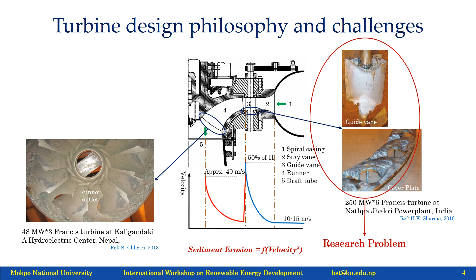So there have been some measurements in the power plants. In the same power plant, the biggest power plant in Nepal, the gap between the guide vane and the cover plate has been measured. So this is the reference line. The initial design clearance gap should be 0.3 millimeters, but due to erosion by the sediments, this gap is increasing, and this has been measured up to 6 millimeters, the total gap. So 3 millimeters on each side is the average gap, and this is due to the erosion of the guide vanes. This is the trailing edge, and that is my focus.